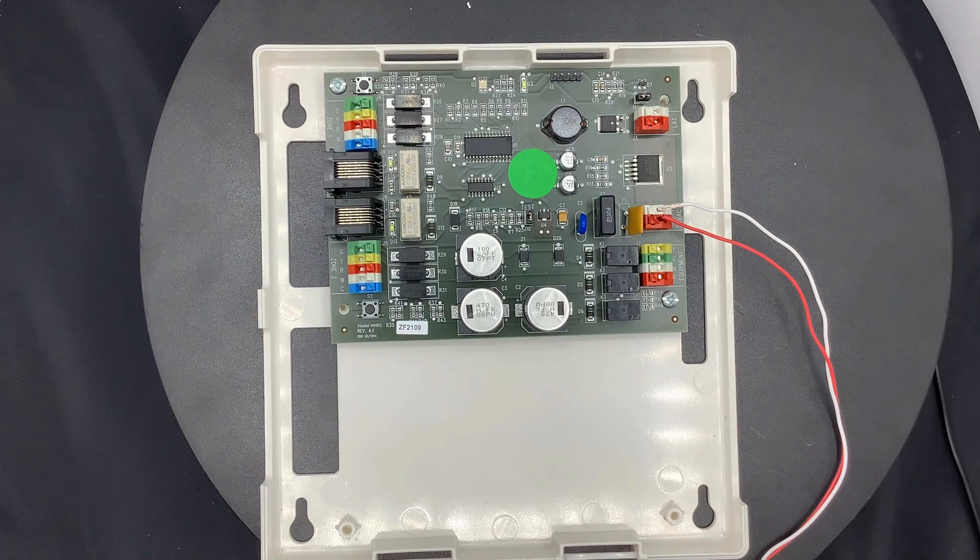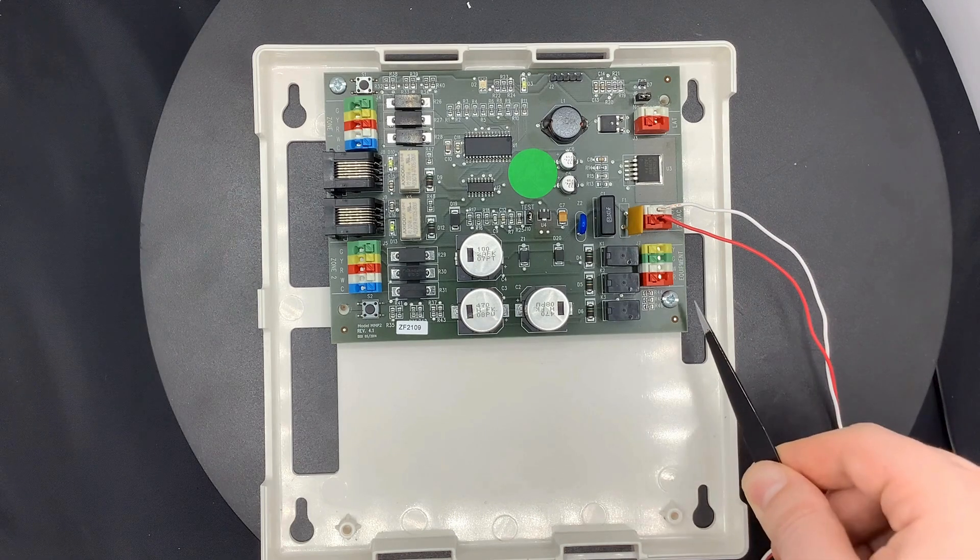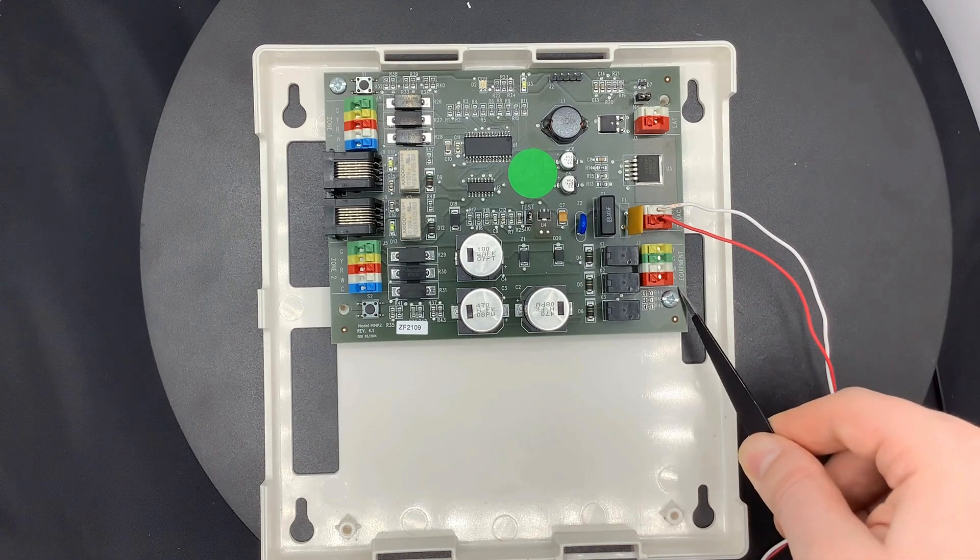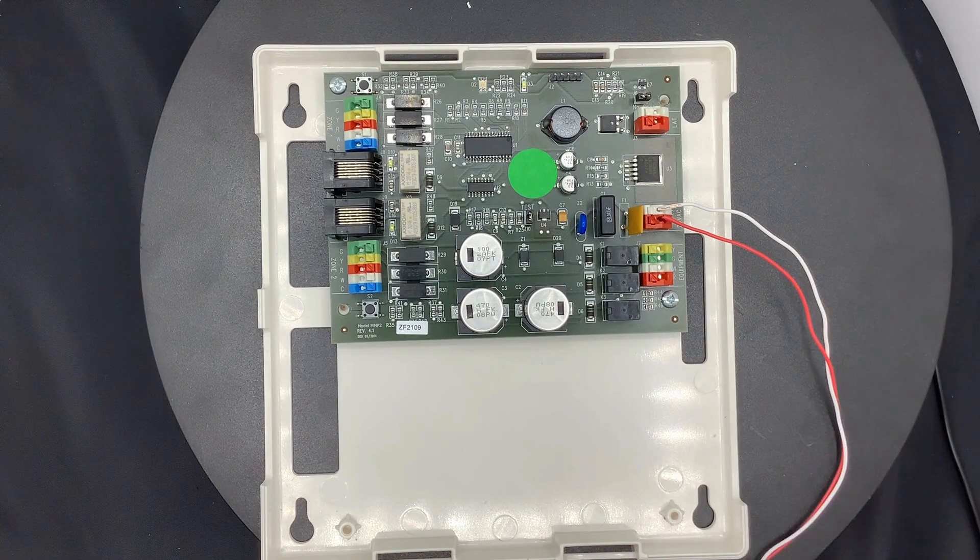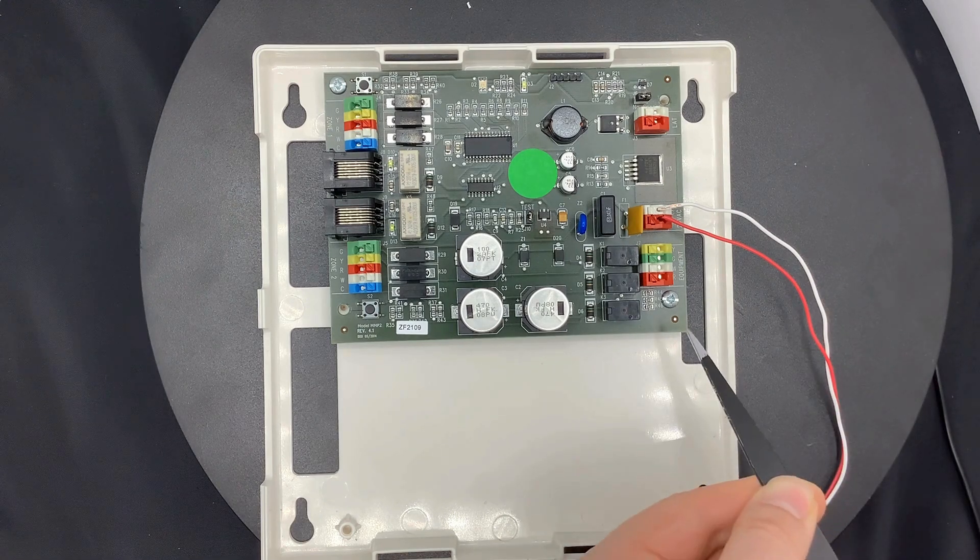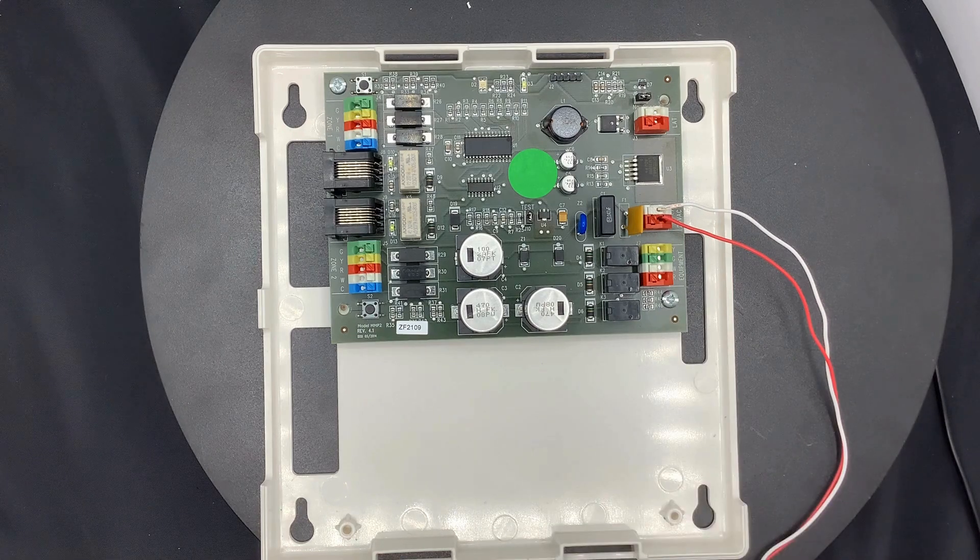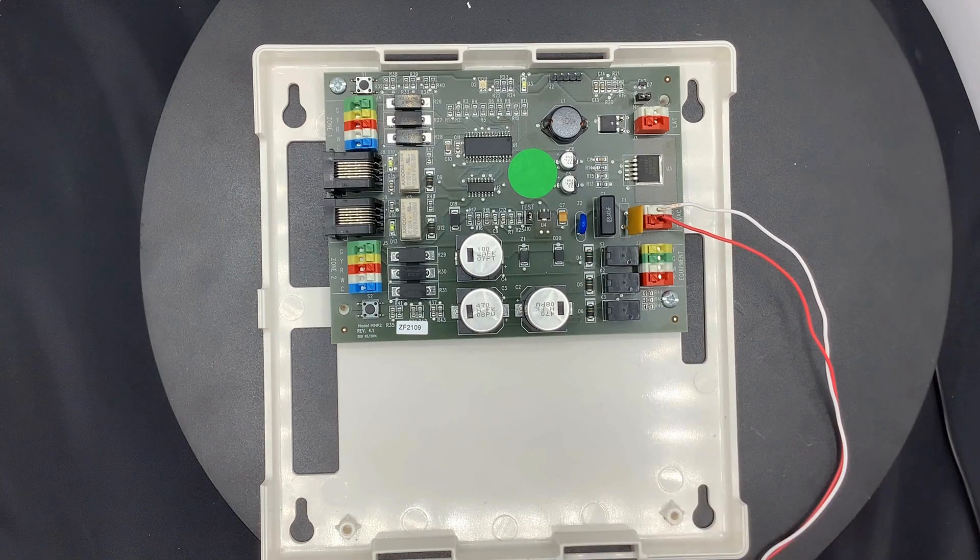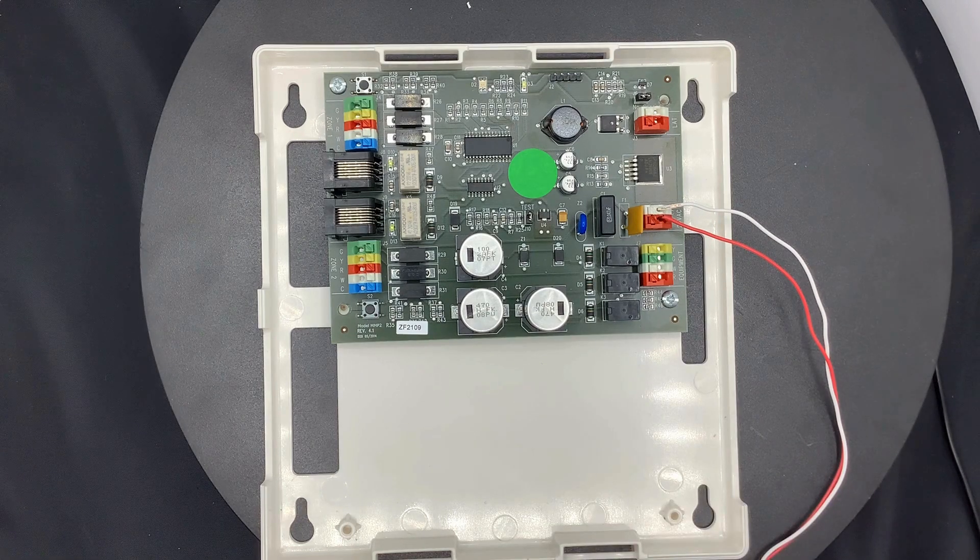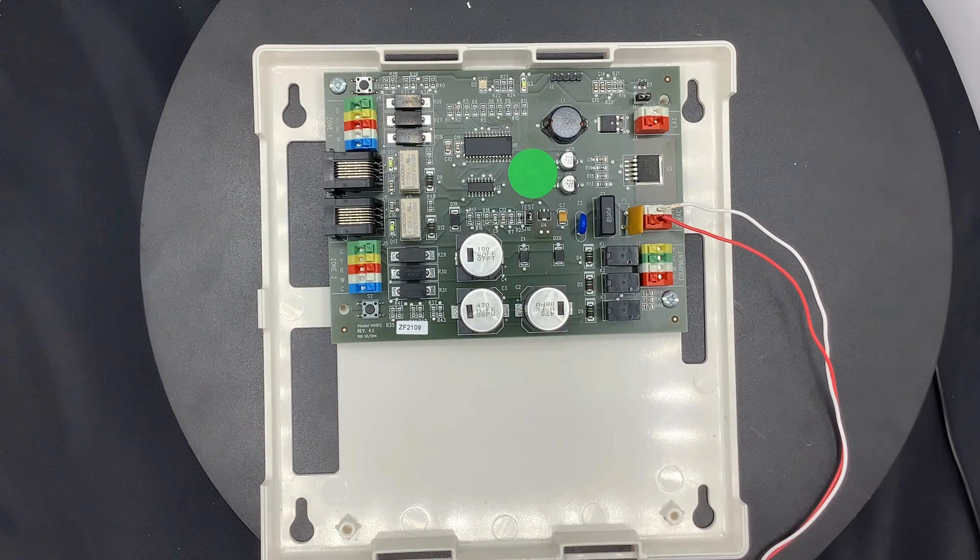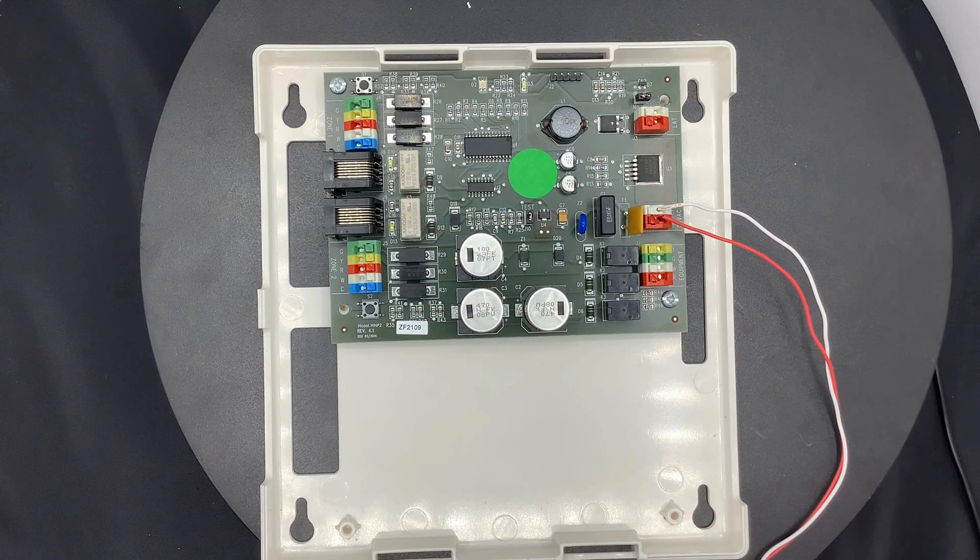Now looking at the right side of the board is the HVAC equipment terminal. As you can see here, there is no common wire, but just an R. That is because this board does not share power with the unit. This board should have its own separate transformer for its power.